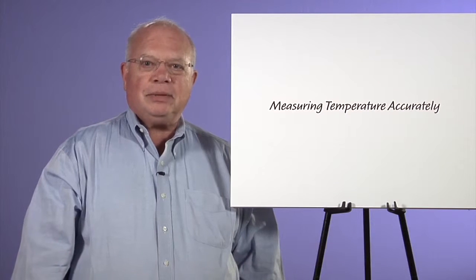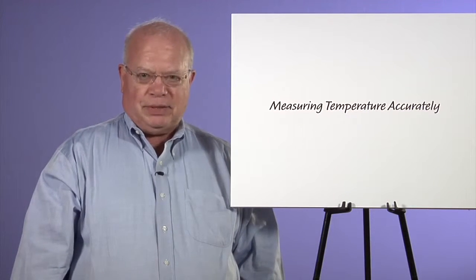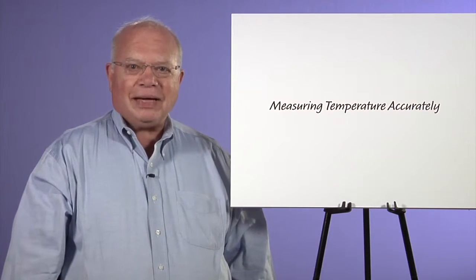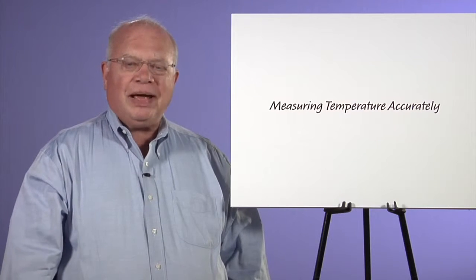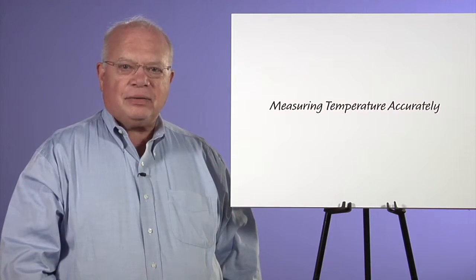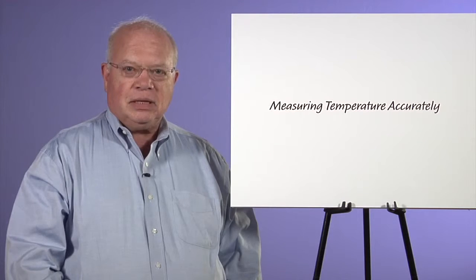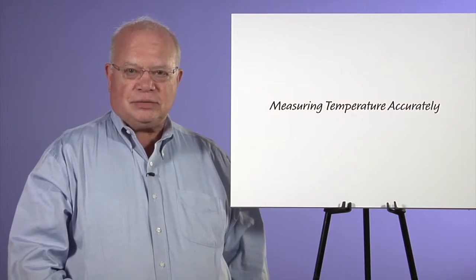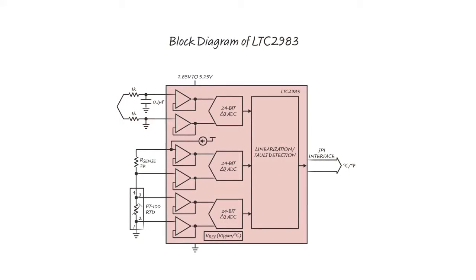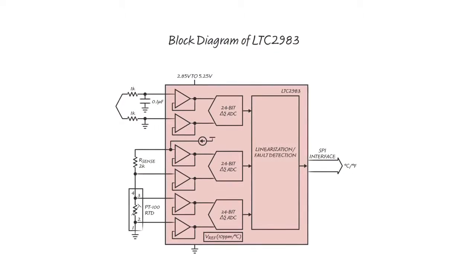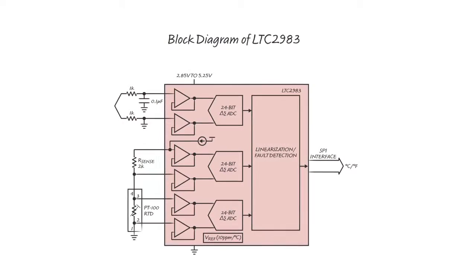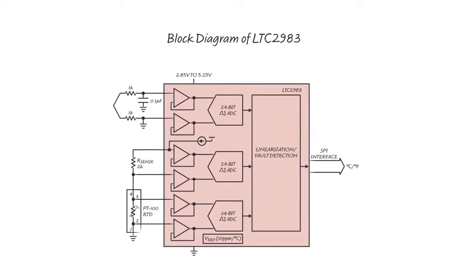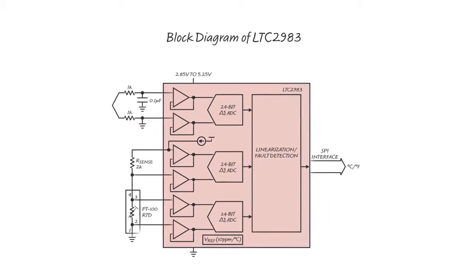I want to talk a little bit about accurate temperature measurement. Because for accurate temperature measurement, we have to have the inaccuracies of the electronics and the inaccuracies of the sensors compensated for. With the LTC 2983, we can get very accurate temperature measurements. Most of the inaccuracies are going to come from the sensors.